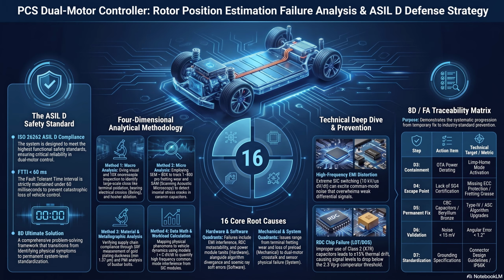Exactly. And if you're looking at page 12 of the research you sent us, they use this EDX process to hunt for something highly specific. They look for localized spikes in oxygen concentration. Right, along sliding tracks on the terminal pins. Sliding tracks that are only like 1 to 200 microns wide. And if you think about it, finding a massive oxygen spike inside an IP67 rated hermetically sealed electrical connector proves you don't have a broad environmental water leak. No, you have a highly localized tribological failure.